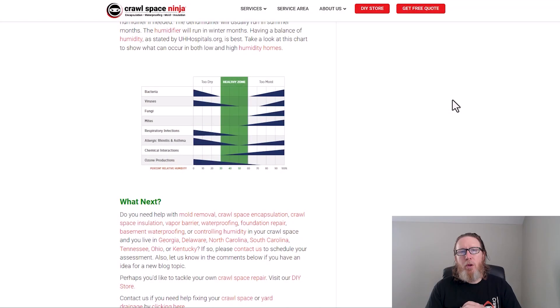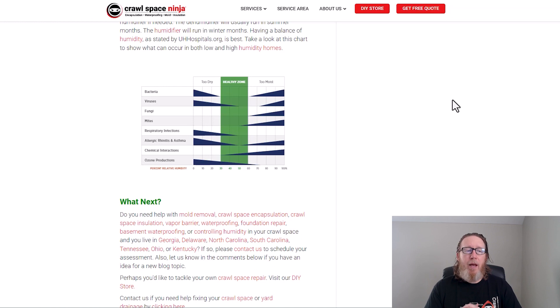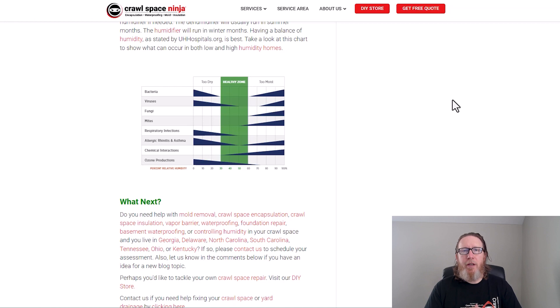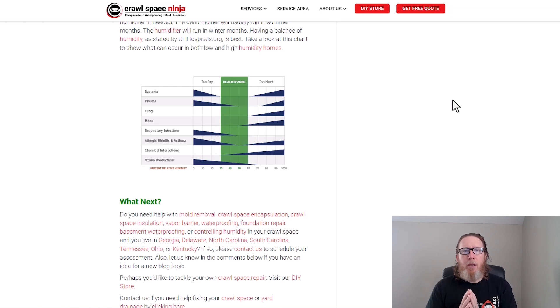That is not the case for mold. I have researched and spoken to microbiologists, and nothing we have seen or heard from any respectable group or organization — other than some salesperson making a claim across the dining room table from you — supports the idea that lowering humidity kills mold. Now there is some possible evidence that lowering humidity does make mold go dormant, but dormancy is not death.